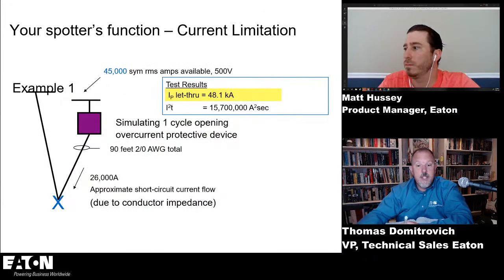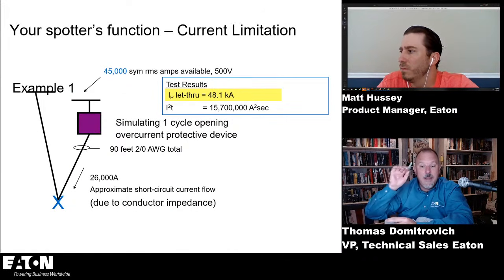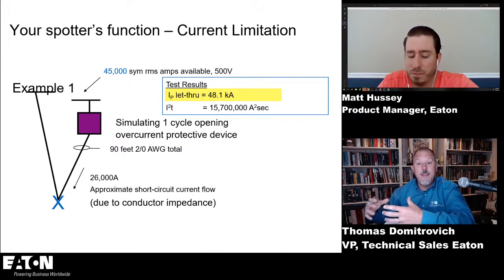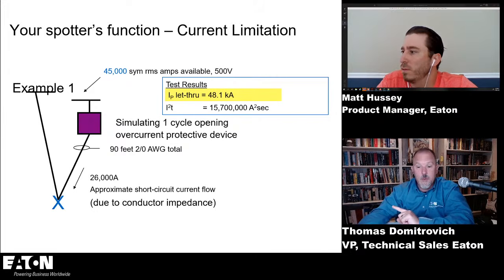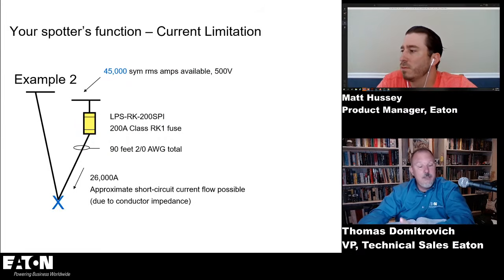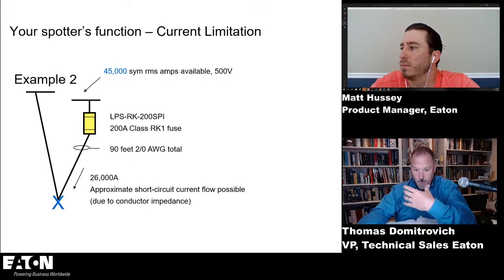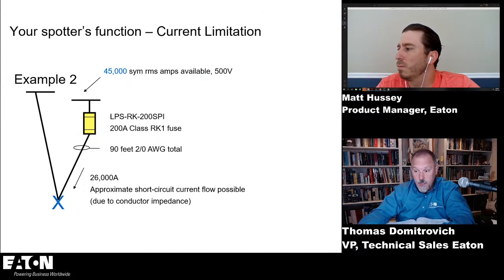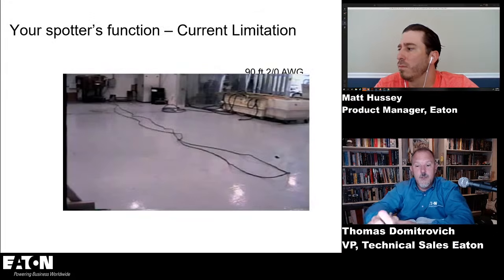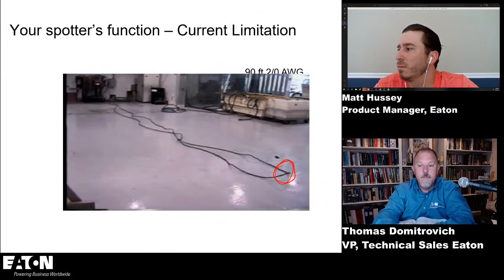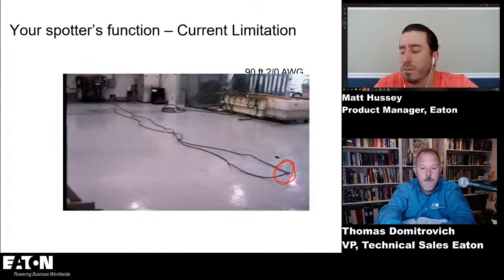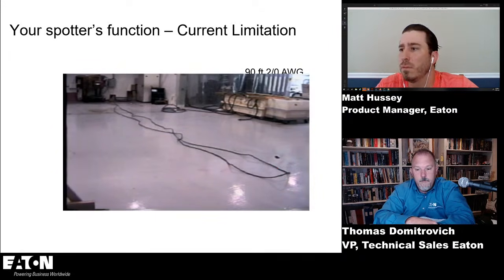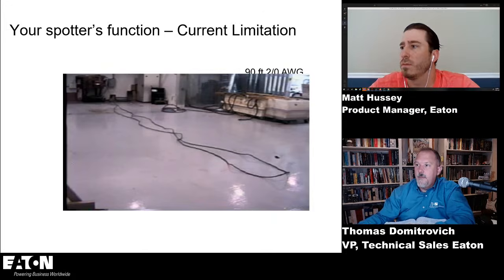And what we show is that the peak let-through that first half cycle was 48,000 amps, and the I squared T, which is the heat, the energy, was 15.7 million amp squared seconds. So then what we do is that exact same test with a 200 amp fuse, which 26,000 amps is going to be well into the current limiting region of that 200 amp fuse. And this is the result, and what you have to do is watch right down here. And there it was. So I'm going to do that one more time in case you missed it. Can I do that one more time?